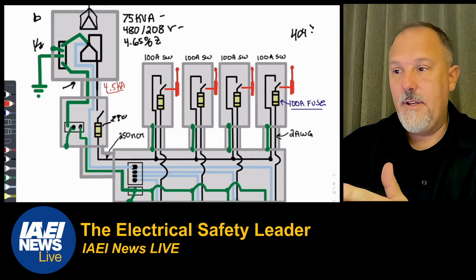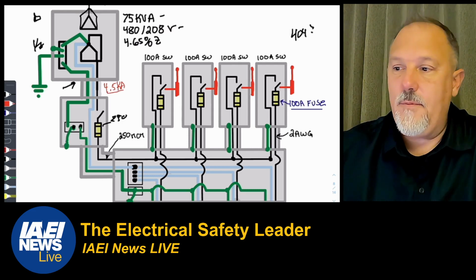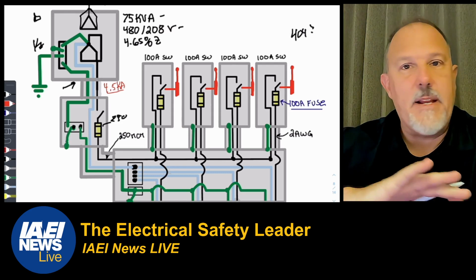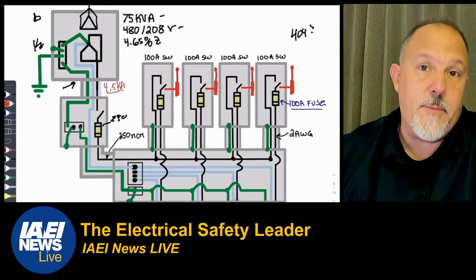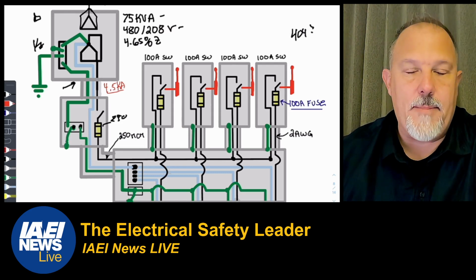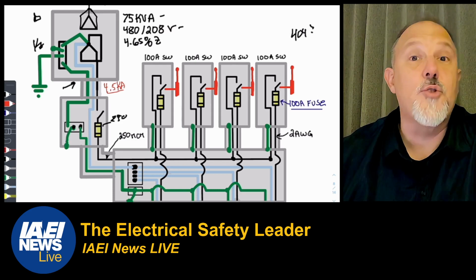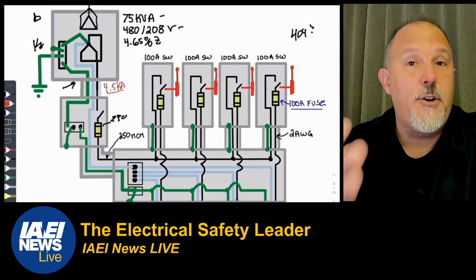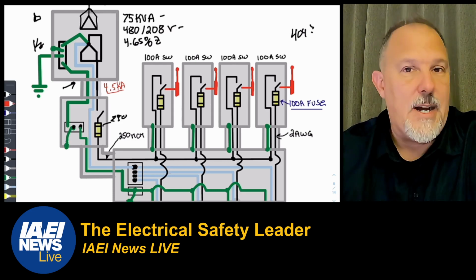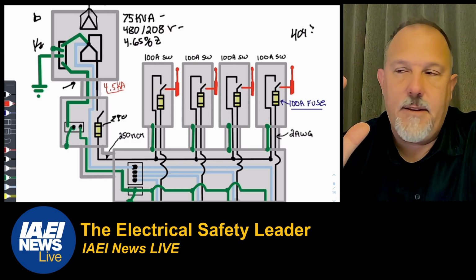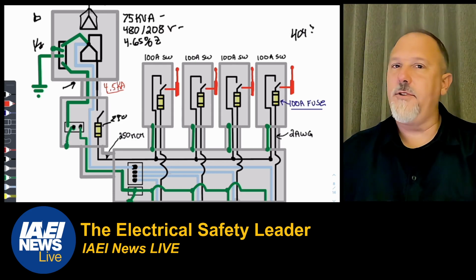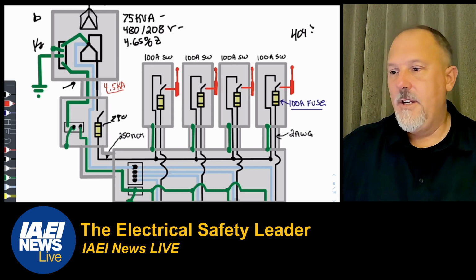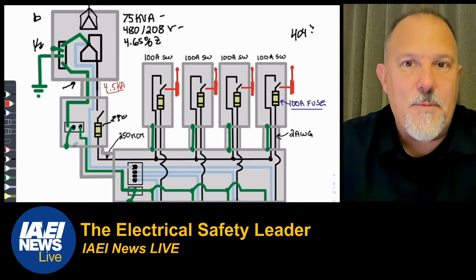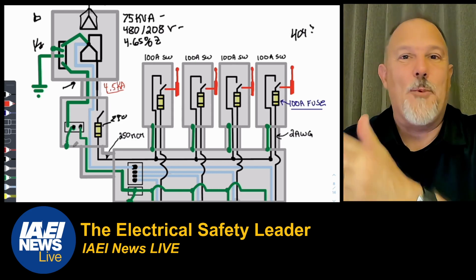So any equipment downstream can be rated 10K, which is pretty much your default. I don't have to worry about any of that equipment from a short circuit current rating perspective. Circuit breakers and fuses, I'm covered. I can get the 10K circuit breakers, no worries. So that helps me now with short circuit current rating, 110.10.